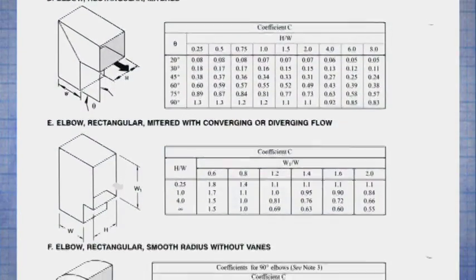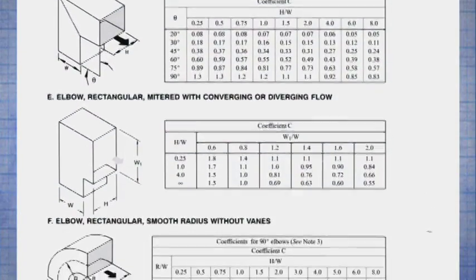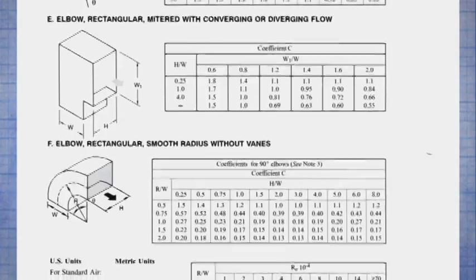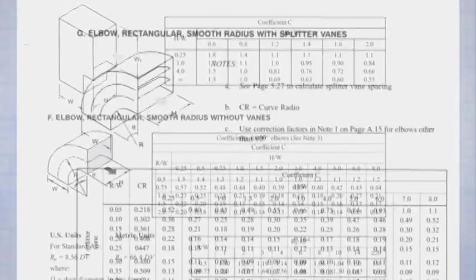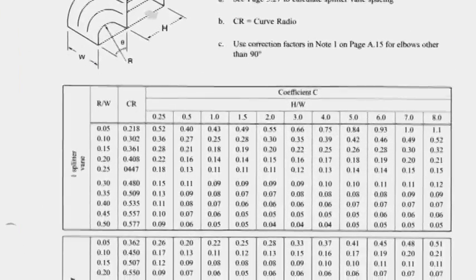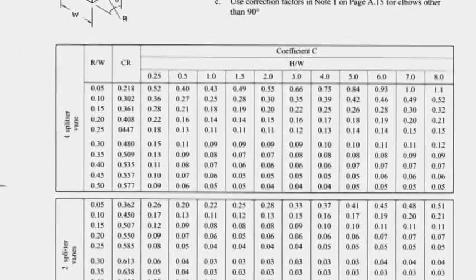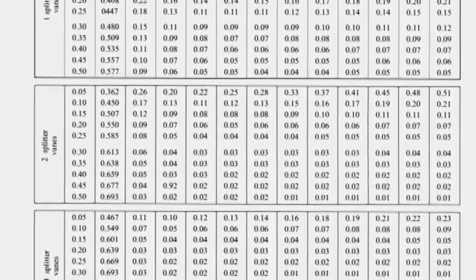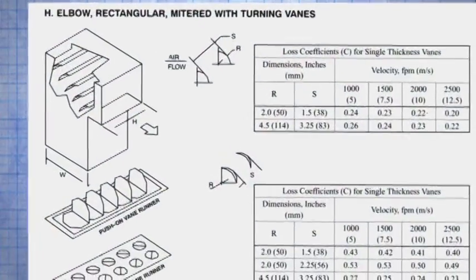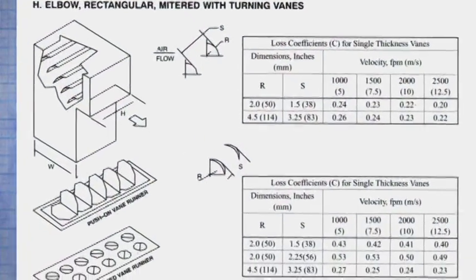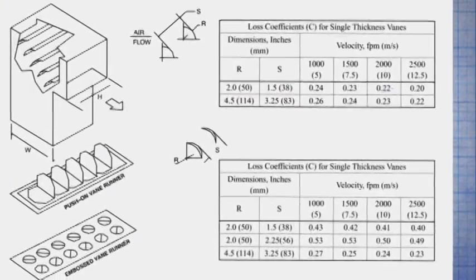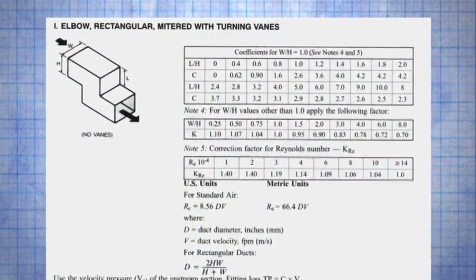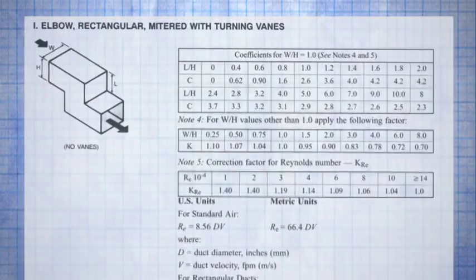These drawings illustrate the fitting types that will be demonstrated and discussed within this video presentation. The drawings were taken from the appendix of SMACNA's HVAC System Duct Design Manual. The data associated with each fitting provides loss coefficient values that can be used to develop the pressure loss contribution of each fitting.